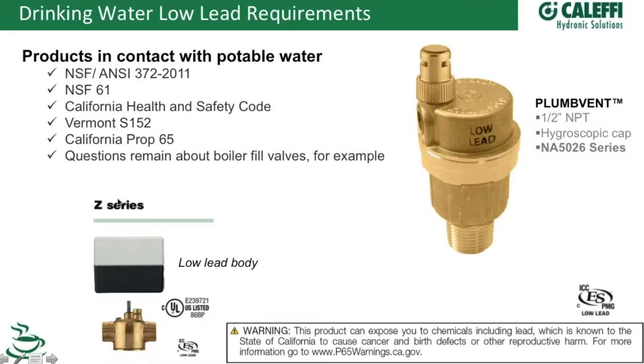On our Z1 zone valve series, this has a couple different standards. The UL listing on this valve has to do with the electrical part — the actuator — not the brass body, although UL could also test the valve for low lead. So this listing would have a couple different numbers: the body has been tested to the NSF 61 ANSI standard, as well as the electrical component — the switch and wiring inside — which has been approved by UL.